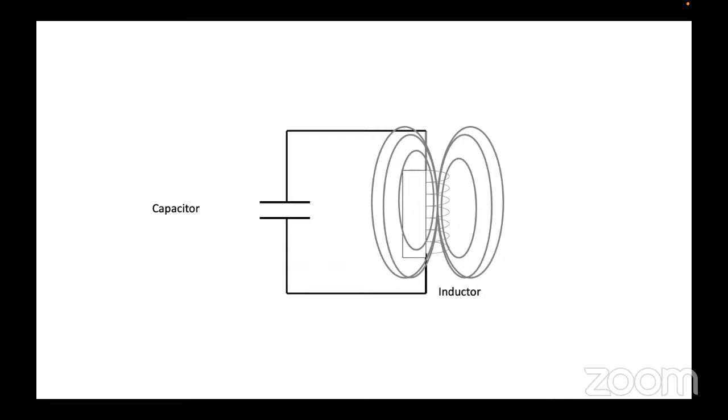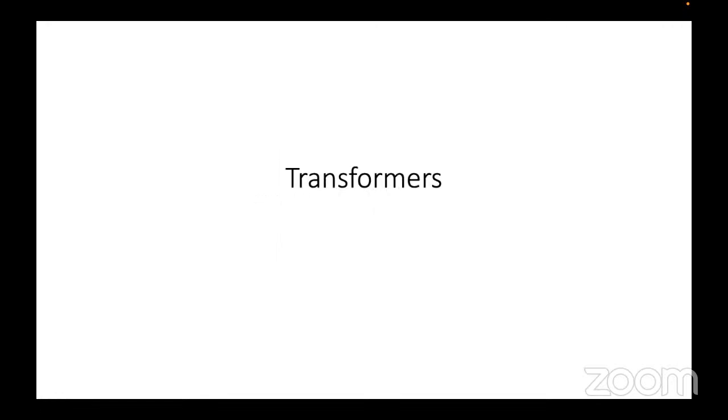If the energy was delivered for just a few milliseconds, the only thing it will do is cause burns on the skin. It will not be conducted to the heart and cause defibrillation. So it's very, very important that this oscillation is maintained. We also talked about the voltage needing to be stepped up from 230 volts to 8,000 volts in the defibrillator, and this is done through transformers.